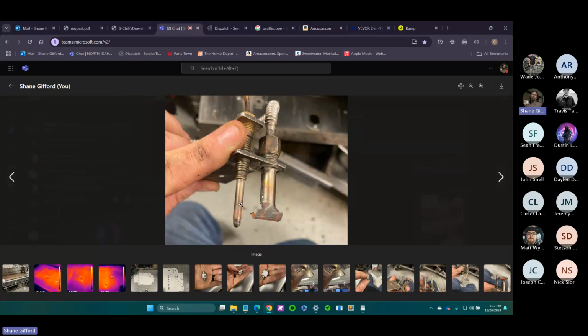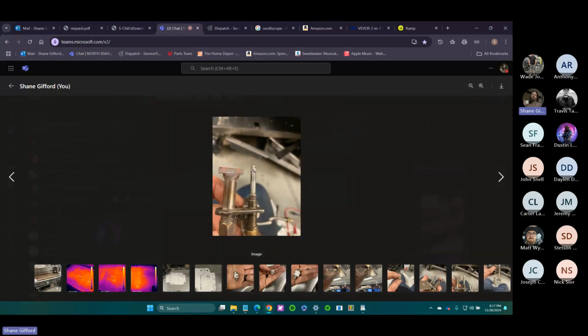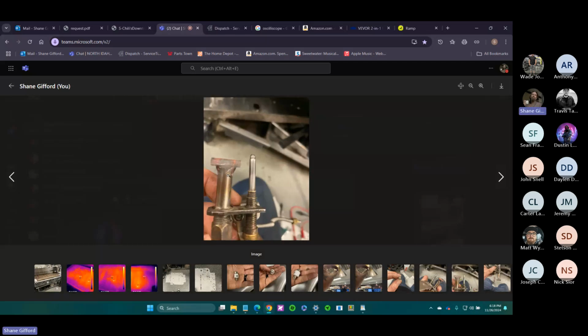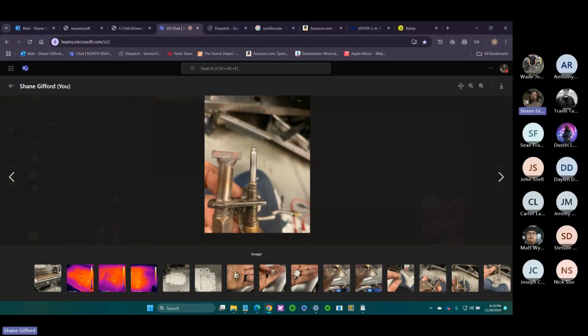Sometimes you'll see over time, pulling these out and cleaning them constantly, you might bend them a little bit. You might mess them up a little bit. Maybe you clean it and put it back in, and your readings are worse. Like, what the hell? It's supposed to be better. Well, you might have accidentally nudged this over or back and forth, and now it's not sitting in direct flame. So make sure that when you put it back in the system, that flame is guaranteed to be hitting that thermocouple. The hood, you don't really got to replace unless you're seeing flame come out of this area. If you're seeing flame spew out of this area, shut it off and change the whole pilot assembly out, hood and all.